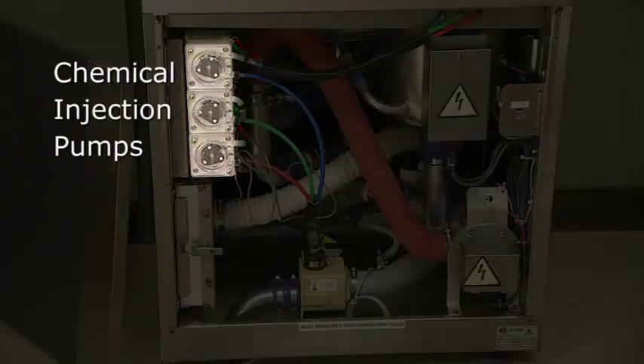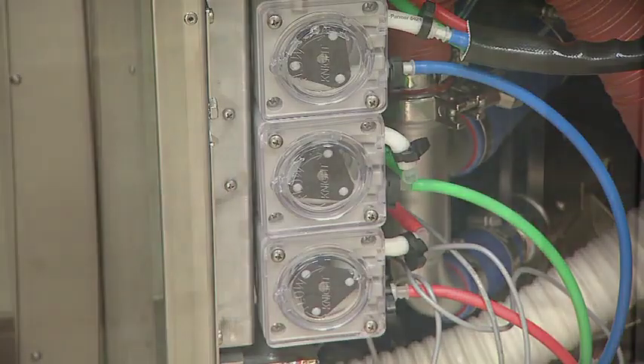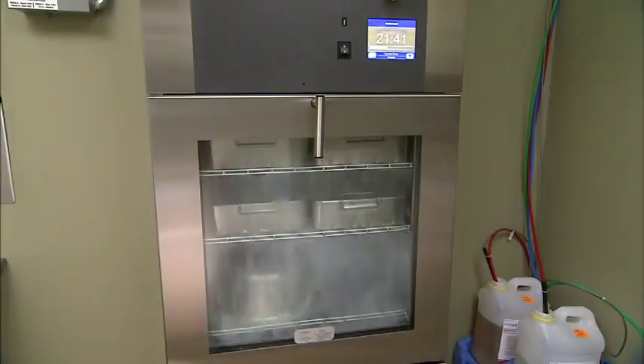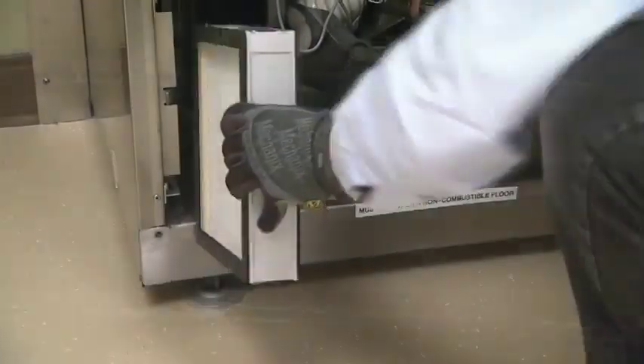Behind the access panels are some important components that will be part of your routine maintenance schedule. On the load side, 3 chemical injection pumps are included in the washer disinfector. These pumps automatically add cleaning chemistry during cleaning and disinfecting cycles. One of the pumps is dedicated to the lubricant to be injected during the thermal rinse phase. Check with your supervisor about the types of cleaning chemistry allowed for use.